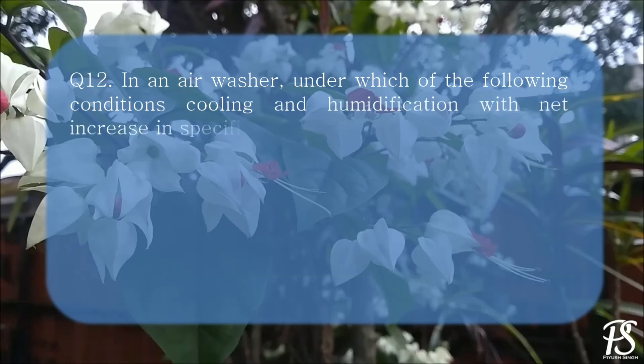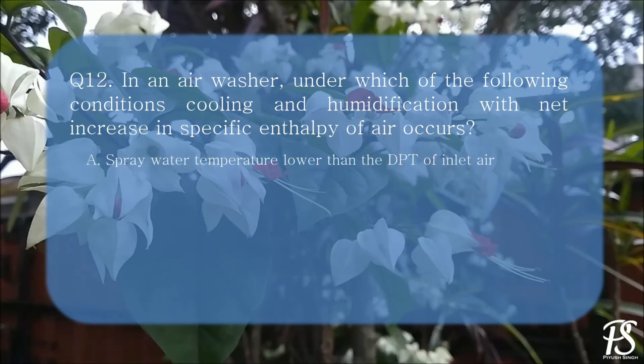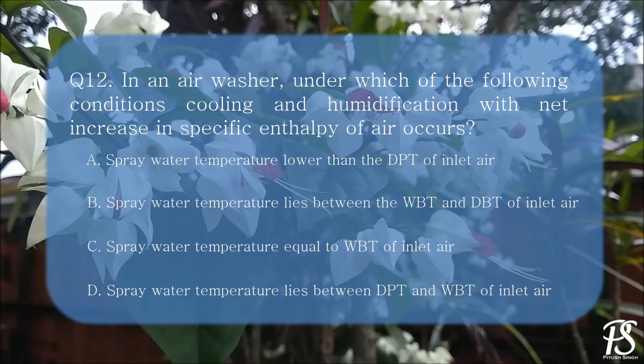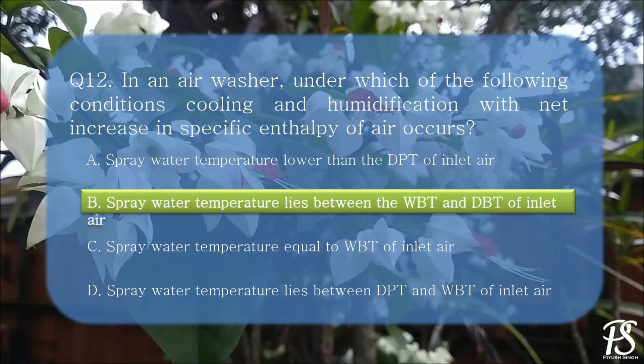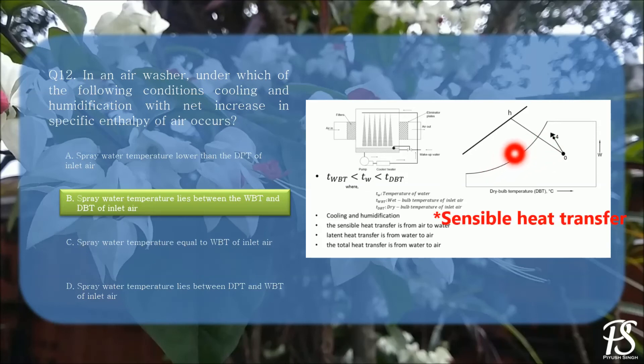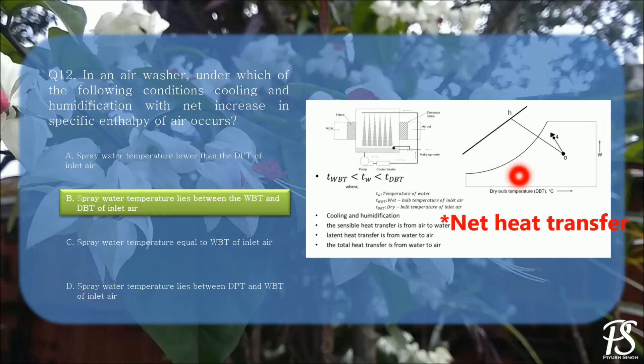In an air washer, under which of the following conditions does cooling and humidification with a net increase in specific enthalpy of air occur? A. Spray water temperature lower than the dew point temperature of inlet air. B. Spray water temperature between wet bulb temperature and dry bulb temperature of inlet air. C. Spray water temperature equal to wet bulb temperature. D. Spray water temperature lies between dew point temperature and wet bulb temperature of inlet air. The correct option is B — spray water temperature lies between the wet bulb and dry bulb temperature of inlet air. In this case, sensible heat transfer is from air to water and latent heat transfer is from water to air, but total heat transfer is from water to air, resulting in increased enthalpy.